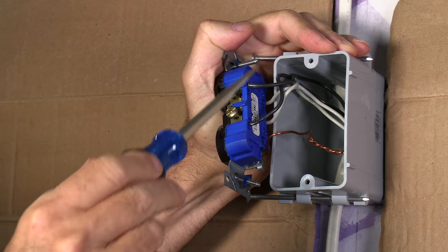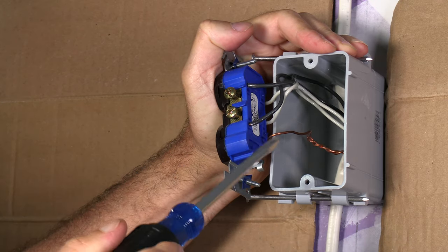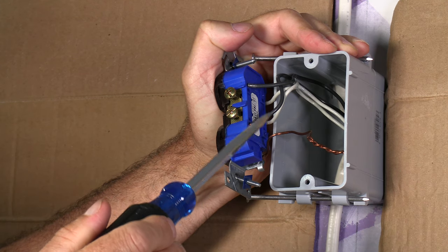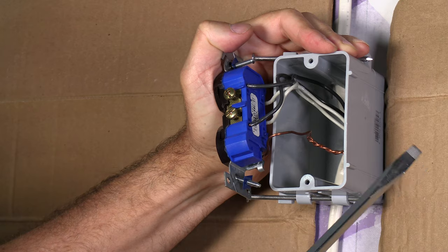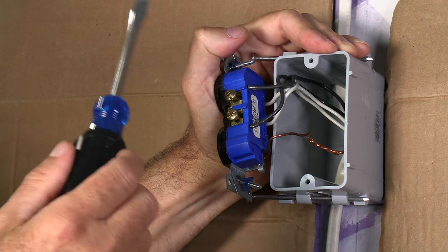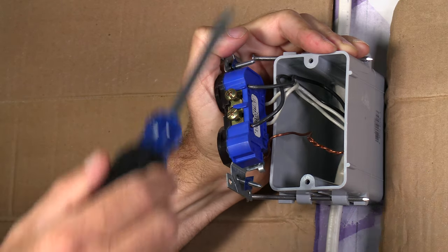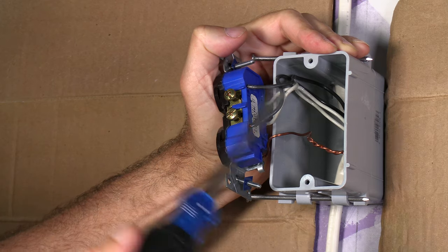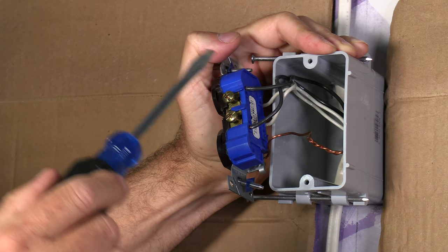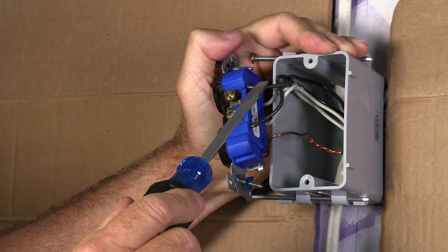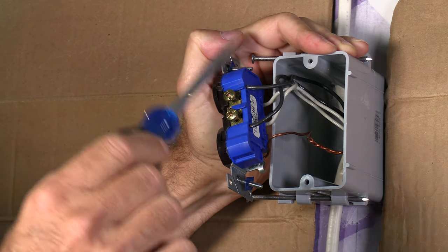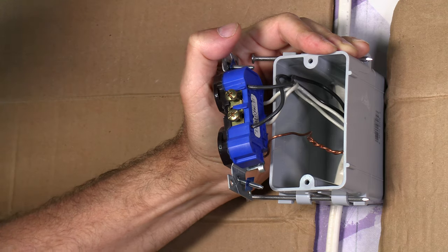But one of these wires could be red. If it's coming from a switch, you may have a switched outlet in case you want to switch a lamp or underneath the countertop, you might have a switched outlet, one going to a garbage disposal, and one going to a dishwasher. Now, if you have that, one of these is always going to be hot. Your always hot wire will go to the black and the red will always go to your switched wire.